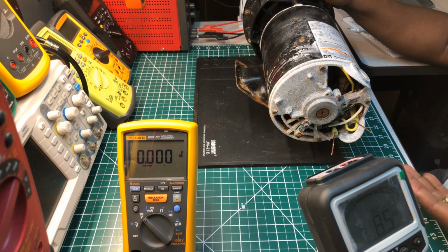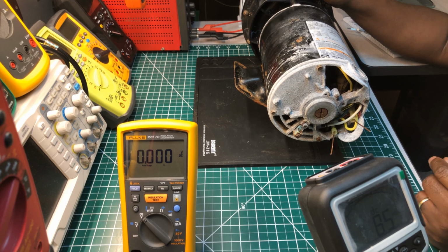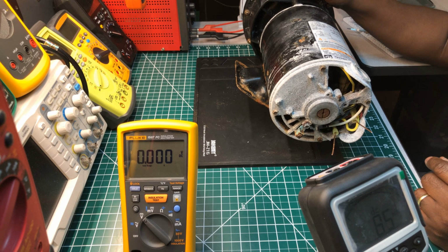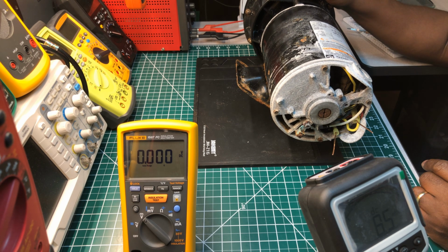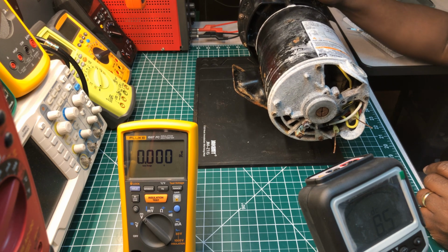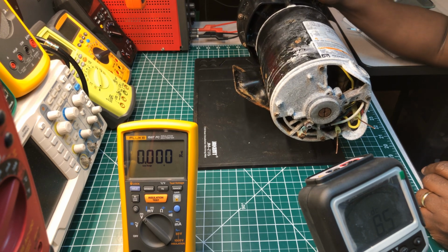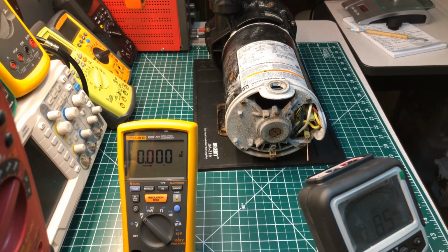Now I'm going to base this test on the IEEE standard 43-2000 that has to do with insulation testing. So I'm going to use that standard when we test the motor, and that's the one I'm going to go by. This is a 115 volt motor, so I'm going to put 250 volts into it, and we're going to see just what they say. The IEEE standard for Class B motors should say what it reads.